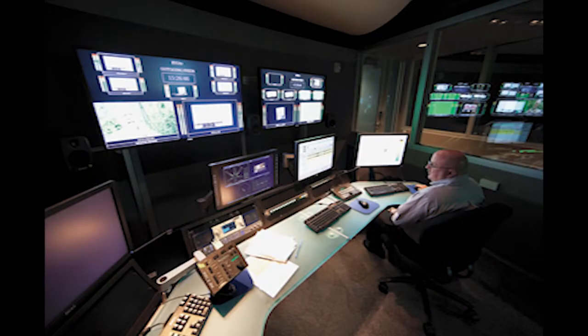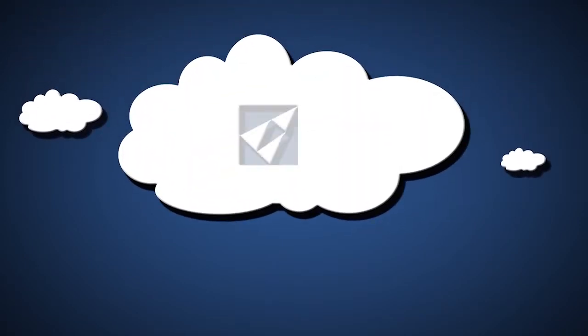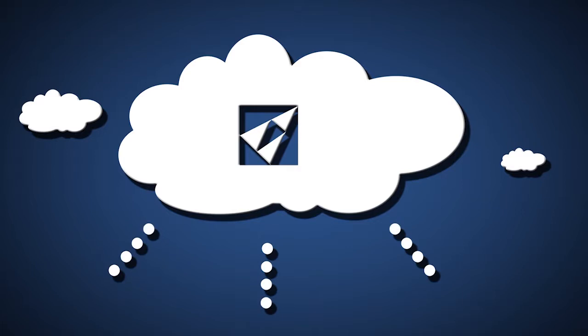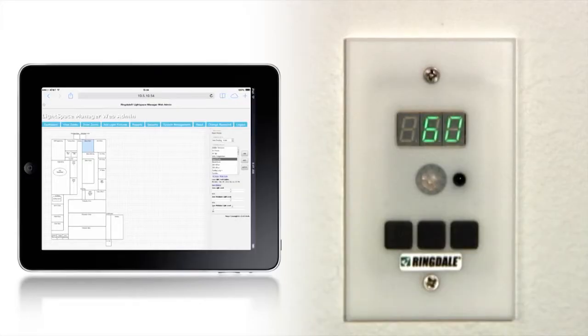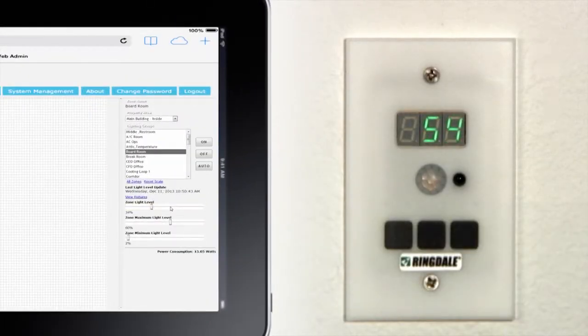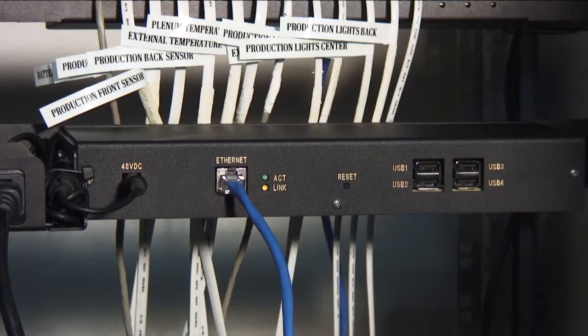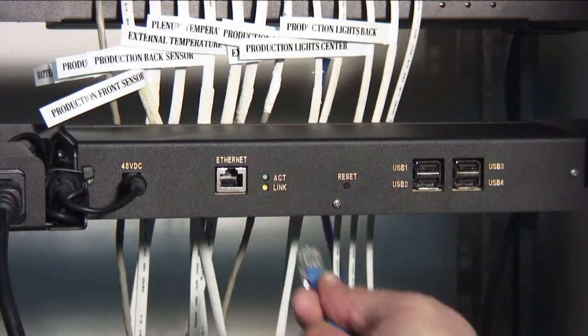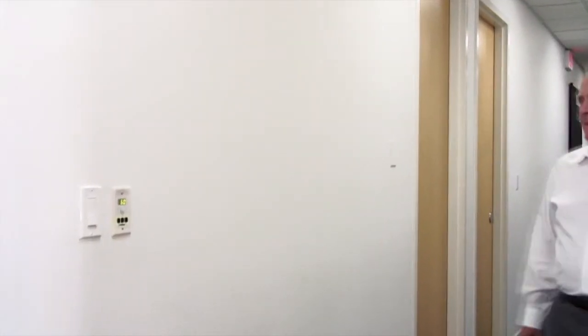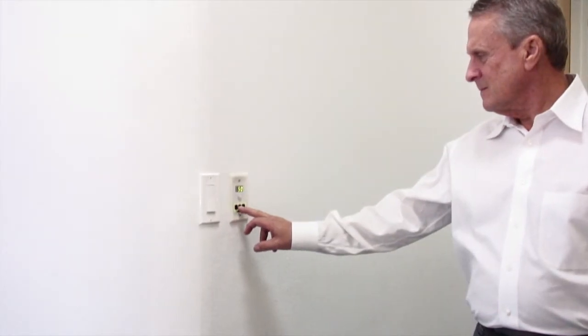Active BMS is ideal for large installations like stadiums where more than one operations room needs to have full access to the system's capabilities. Active BMS also lends itself to be used in centralized applications where multiple sites are controlled from one or more servers in the cloud, so no local server is required. A fail-safe strategy allows local control when no server access is available, as well as the ability to use LSC and relay controller devices as programmable logic controllers, also known as PLCs, where the local program takes over if connection to the server is severed or temporarily not available.